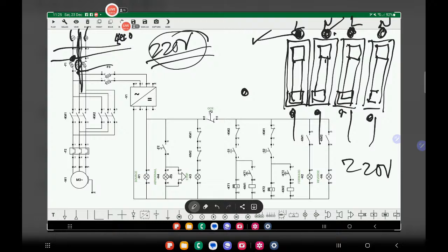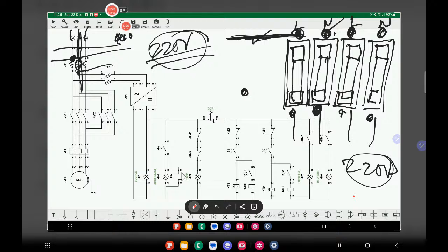So if I check which one is busted, if I leave my probe here and move it onto the N, I'm having 220. Then the next one, so I'll change the color so that I'll repeat it again. If I put my probe into the first point, and the second probe of my multimeter onto the output line of the neutral, then I have 220 volts, then this fuse is okay. I hope you get it now. This is especially for the beginners.